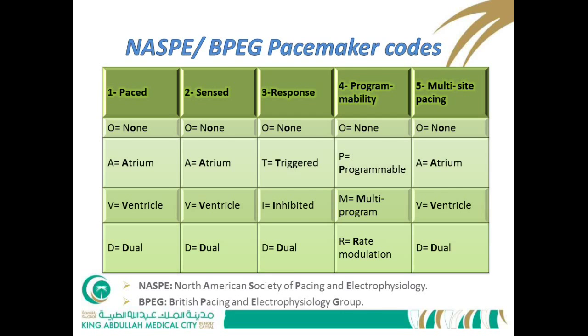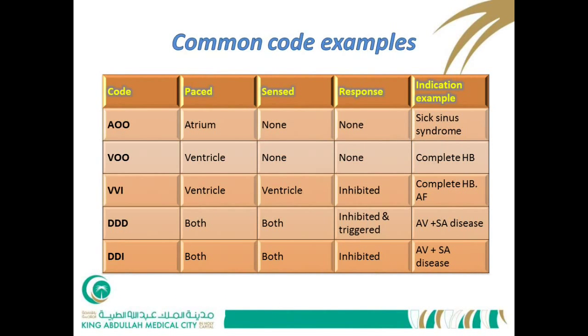Common code examples include AOO or VOO — the asynchronous mode — where the atrium or ventricle is paced without sensing or response. VVI means the ventricle is both paced and sensed; if the ventricle has its own electricity, the pacemaker senses it and is inhibited, not delivering its own stimulus.